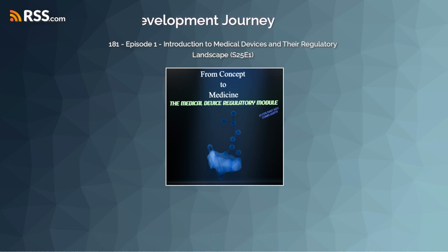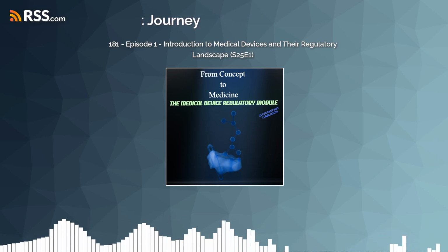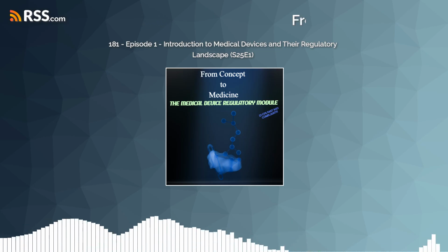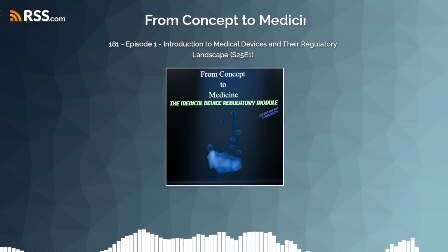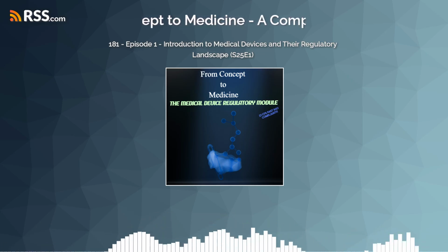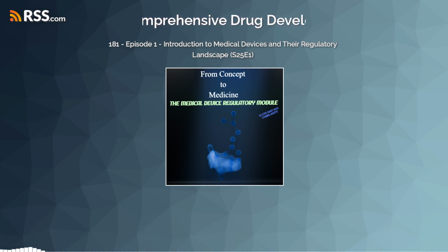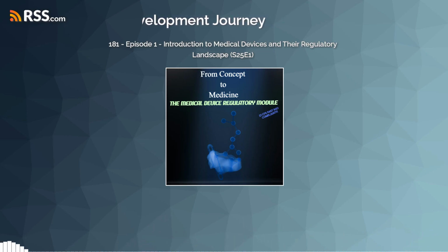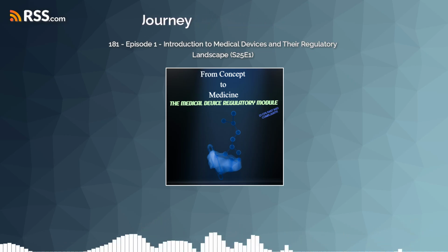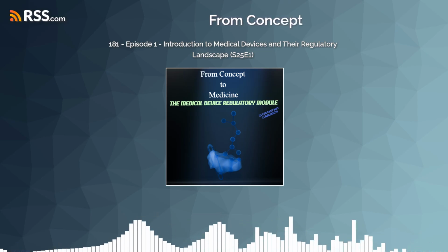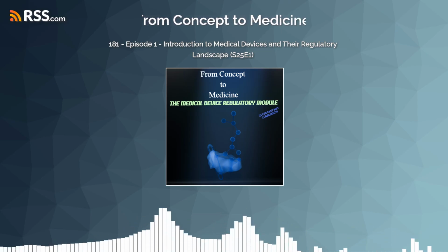Prove the process. And I imagine keeping track of each individual device produced is vital, like a unique record for every unit. Absolutely essential. A device history record, or DHR, must be maintained for each individual device, or sometimes each batch or lot. The DHR. This record contains all the details: the manufacturing dates, the quantity manufactured, the quantity released for distribution, all the acceptance records showing it met the DMR specifications. It's the individual device's production story, providing traceability.